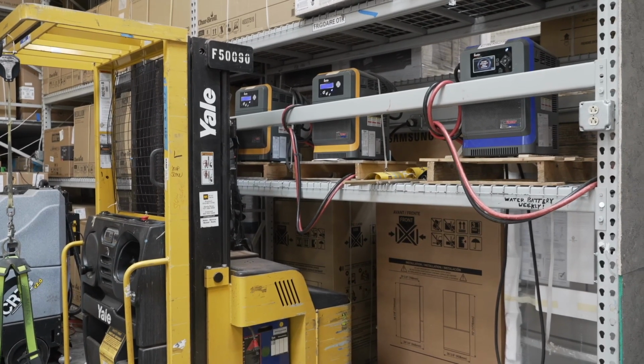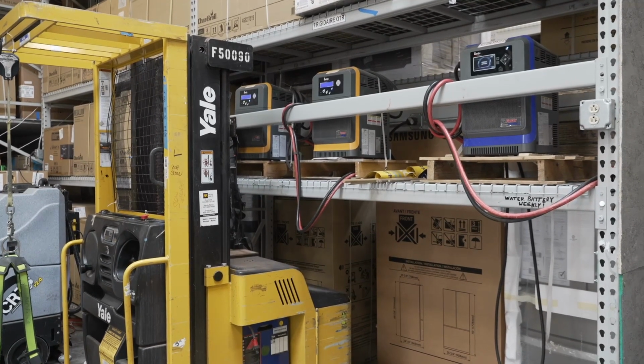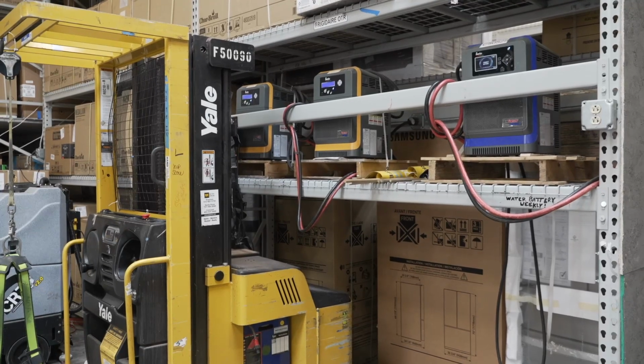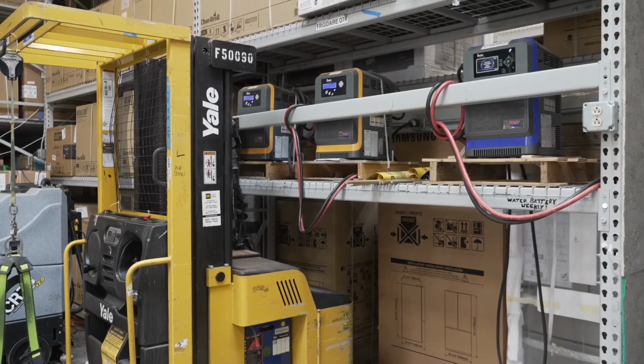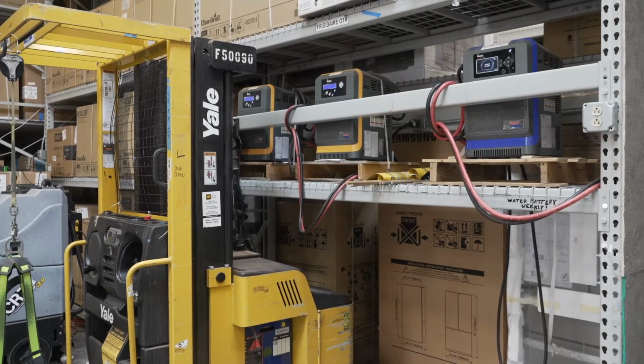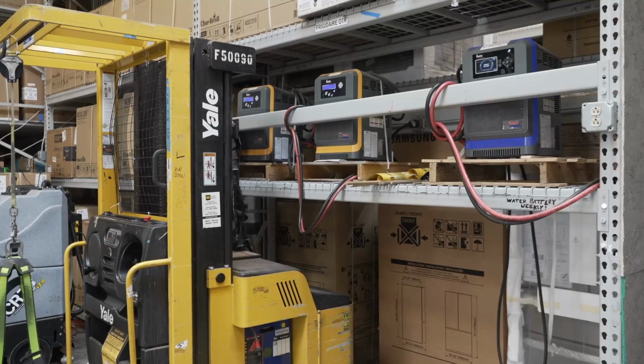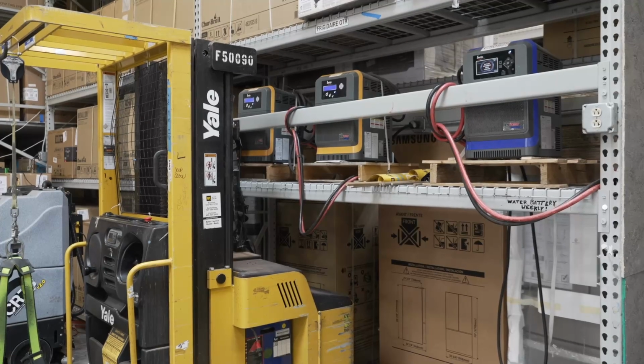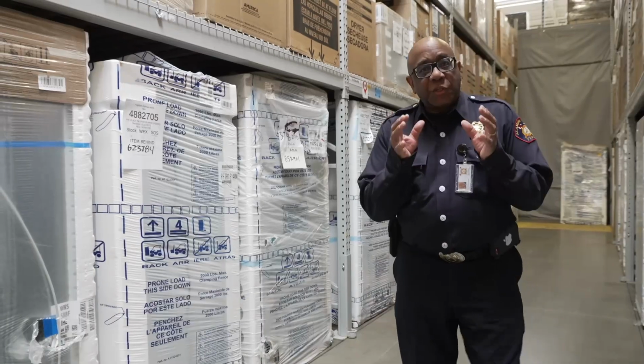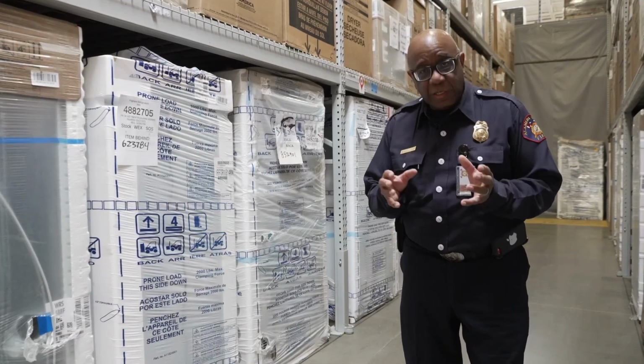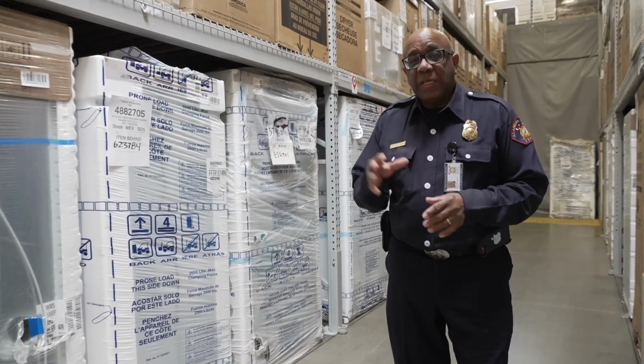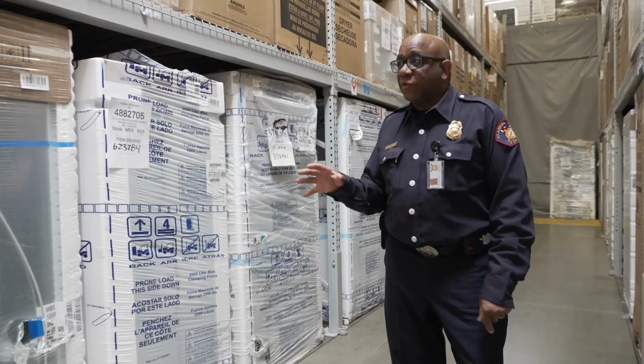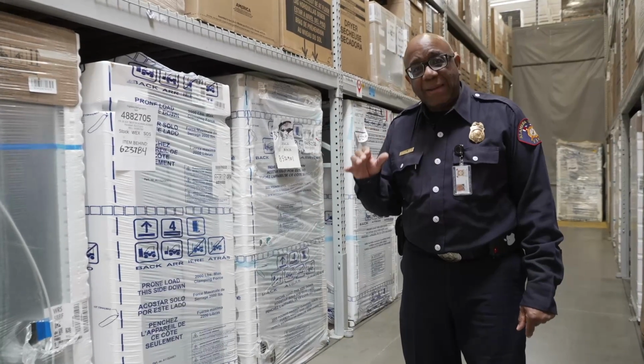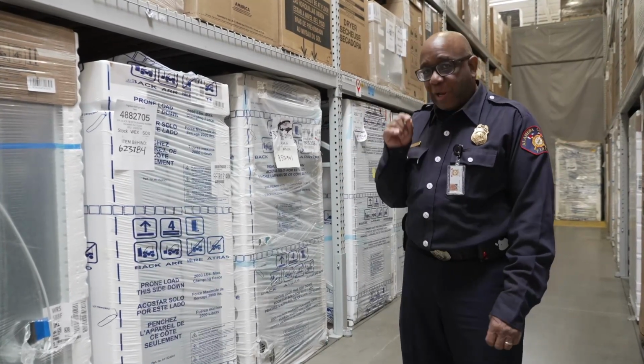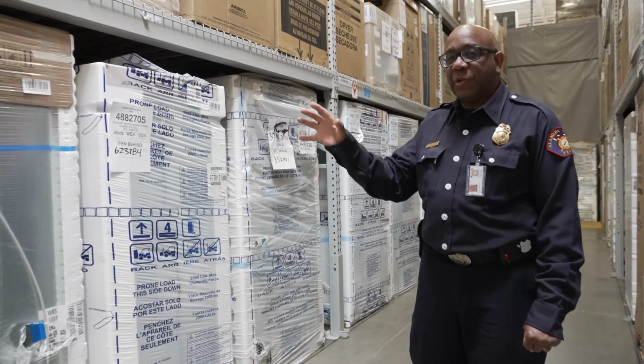Material handling equipment is usually electric inside the building and propane or diesel exterior to the building. In this case here, this is electric material handling equipment. You want to make sure that none of the cables are damaged and that it is properly connected to the suitable electric power. Something to keep in mind when you're doing your inspections of big box stores is your back of house storage is going to be very highly dynamic from your fire protection standard. If your sprinkler system isn't up to snuff, look what you have here.